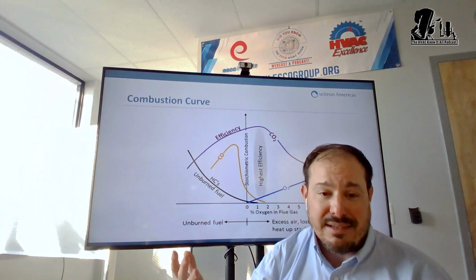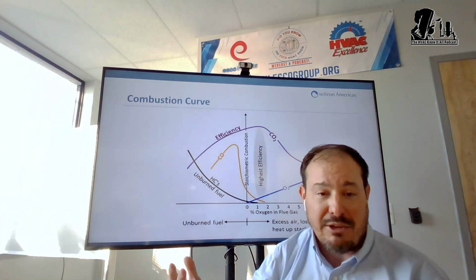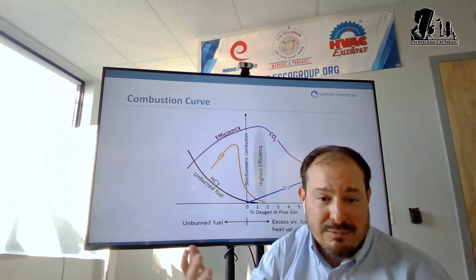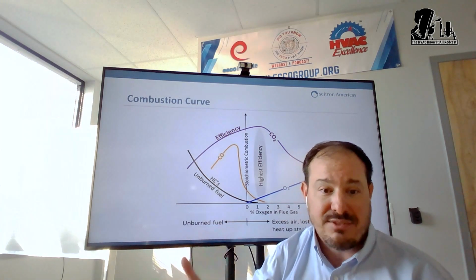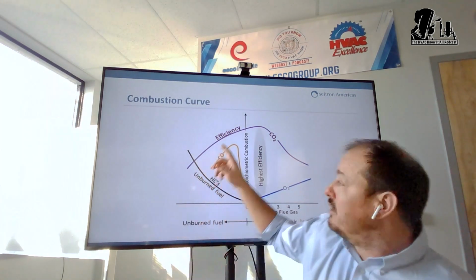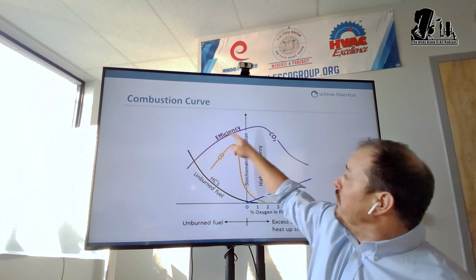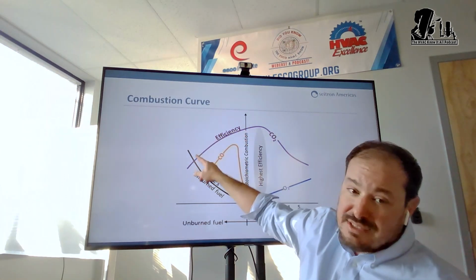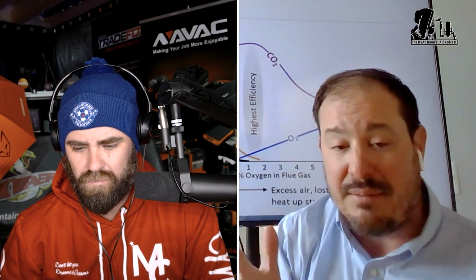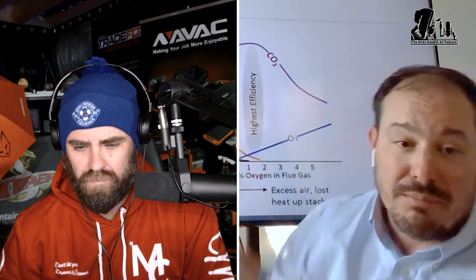Well, I got to tell you something. About 95% of the analyzer manufacturers out there, there's nobody that has a CO2 sensor. And the reason being is, if you look at my curve at the top, where you see the CO2 and efficiency curve, they're in essence one and the same. CO2 tells us the efficiency, but the curve is the problem.